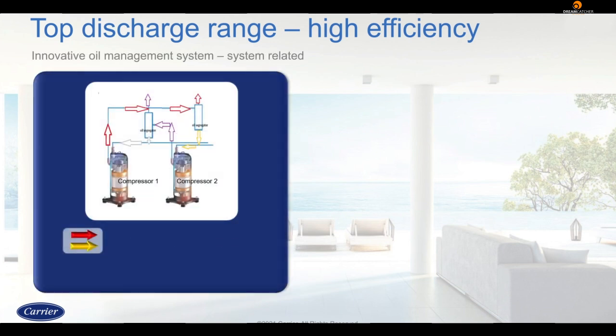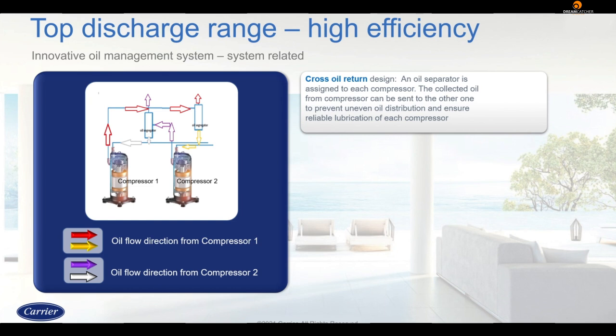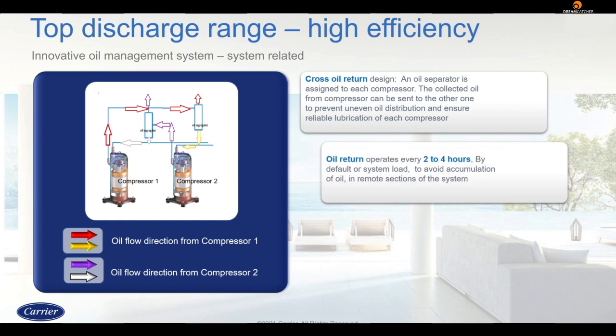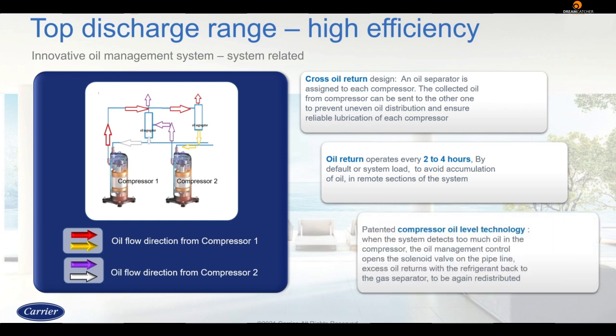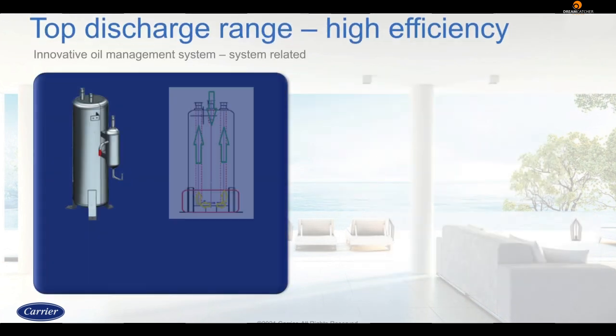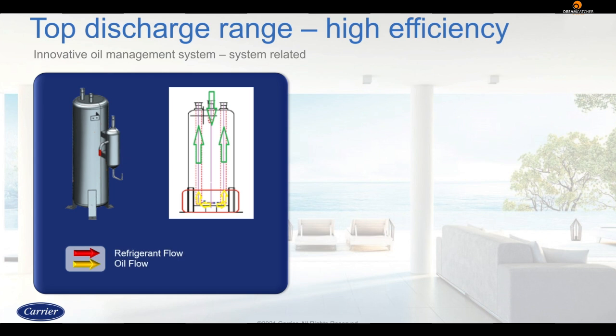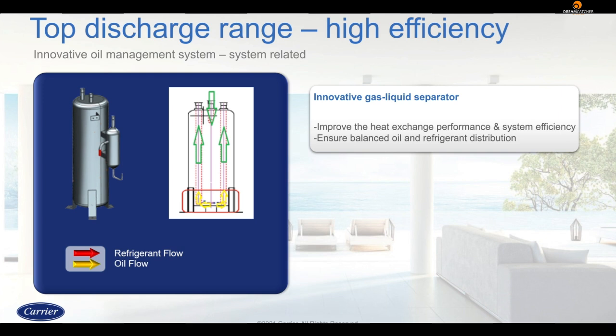What increases the efficiency of the XCT7 even more is a cross-oil return design, in which an oil separator is assigned to each compressor. This way, the collected oil can be exchanged between each other to prevent uneven oil distribution. The oil return is operated every 2 to 4 hours to ensure reliable distribution of oil across the system. The patented compressor oil level technology opens the solenoid valve on the pipeline when it detects too much oil in the compressor. This ensures that the excess oil is sent back to the gas separator with the refrigerant to avoid any wastage. In addition to that, the innovative gas liquid separator improves the heat exchange performance and system efficiency and ensures a balanced oil and refrigerant distribution.